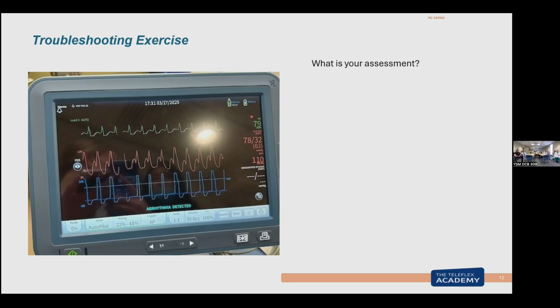Right now, the pump is pumping, but if his heart rate got faster, the problem will be I may not have enough time to get back to baseline. I will get a possible helium loss alarm, because I have to get back to baseline before I start my next inflation. And if I can't, then I need you to figure out why I can't get back to baseline. Typically, the most common place for the kink is not external. If the tubing is straight, it's not kinked. The most common place is right at the groin site. So either a steep angle of insertion or tortuous anatomy, which they all had normal anatomy, but they don't. So anything that's causing my helium to slow in and out. Angle of insertion is very important for us to remember.